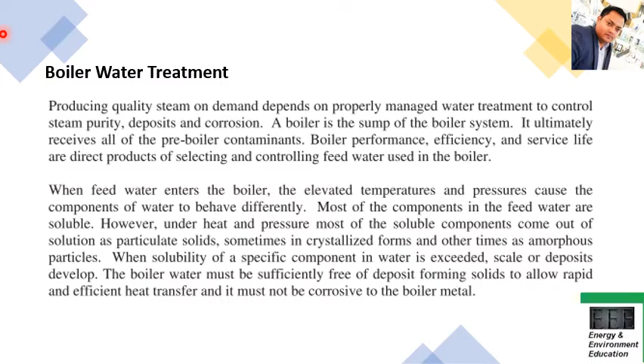So as I said in the last slide, you need to understand that water quality is very much important, and for that, why it is important, because the deposits or scale formation is avoided if the water quality is good enough. So the deposit control that you are having here also needs to be understood and controlled, how much deposit it is having after the water gets evaporated. Deposits in boiler may result from hardness contamination of feed water and corrosion products from the condensate and feed water system. Hardness contamination of the feed water may arise due to a deficient softener system. I mean, if the softener system is not efficient enough, in that case, what happens? It will not soften the water. In that case, there will be hardness in the water, and this will result in the deposit formation inside the boiler chamber, friends, once the water is evaporated.